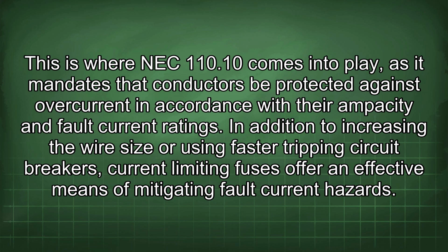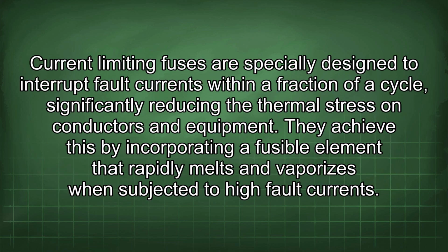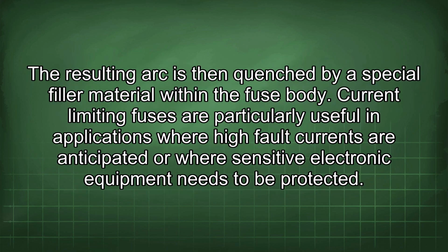In addition to increasing the wire size or using faster tripping circuit breakers, current-limiting fuses offer an effective means of mitigating fault current hazards. Current-limiting fuses are specially designed to interrupt fault currents within a fraction of a cycle, significantly reducing the thermal stress on conductors and equipment. They achieve this by incorporating a fusible element that rapidly melts and vaporizes when subjected to high fault currents. The resulting arc is then quenched by a special filler material within the fuse body.